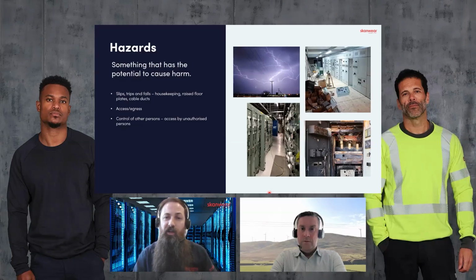So you could have multiple on an outage, which again we've mentioned are at a premium. They don't come along very often. To minimize downtime, you're going to try and maximize as much as you can in that window. So you might have people maintaining the variable speed drives, the cast resin transformers, the LV gear, the MCC. You could have multiple work parties in there, which introduces hazards that individual work parties or work planners might not have considered. So control of authorized persons is just as important as unauthorized persons.